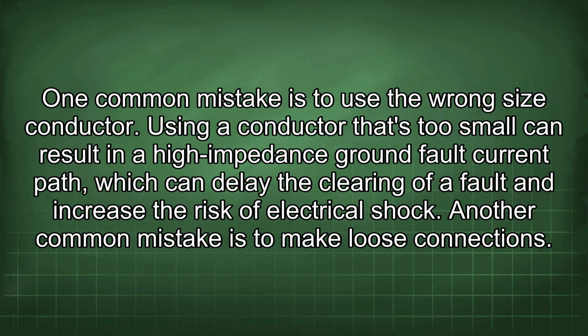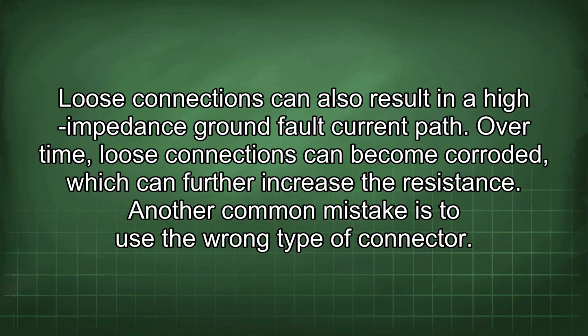Another common mistake is to make loose connections. Loose connections can also result in a high impedance ground fault current path. Over time, loose connections can become corroded, which can further increase the resistance.